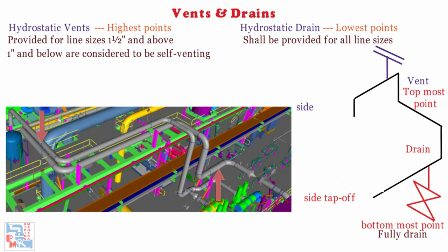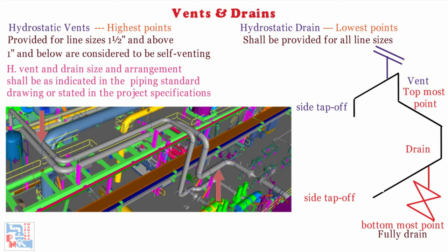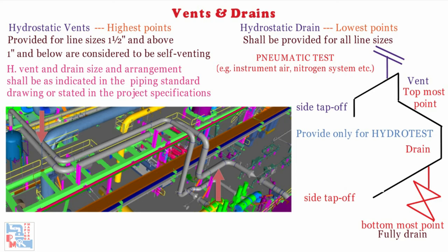The hydrostatic vent and drain sizes and arrangements shall be as indicated in the piping standard drawing or stated in the project specifications. Hydrostatic vents and drains shall be provided for the piping system subjected to hydrotest. If the piping system is subjected only to pneumatic tests — for example, instrument air, nitrogen system, etc. — then hydrotest vents and drains need not be provided.